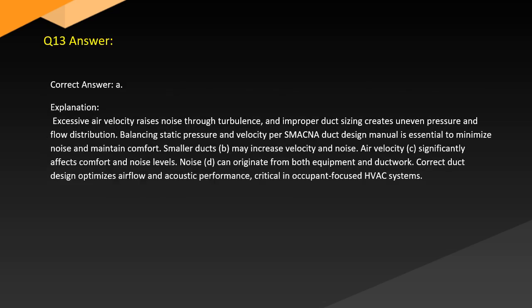Answer. Correct answer: A. Explanation. Excessive air velocity raises noise through turbulence, and improper duct sizing creates uneven pressure and flow distribution. Balancing static pressure and velocity per the SMACNA duct design manual is essential to minimize noise and maintain comfort. Smaller ducts, B, may increase velocity and noise.